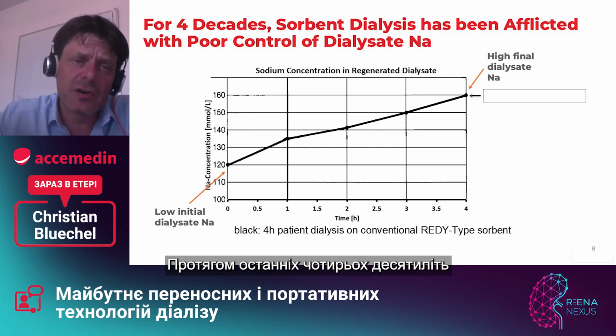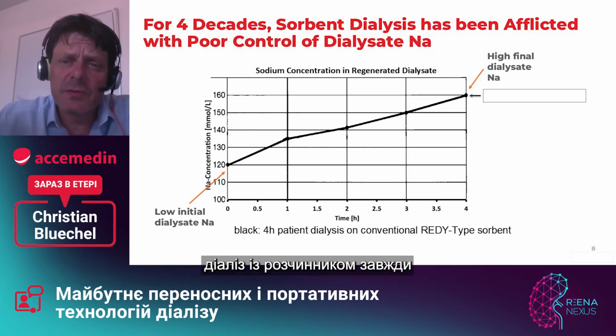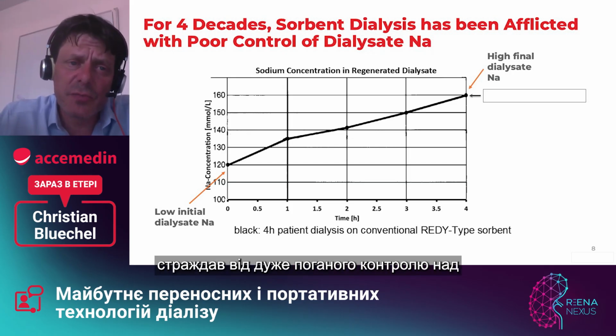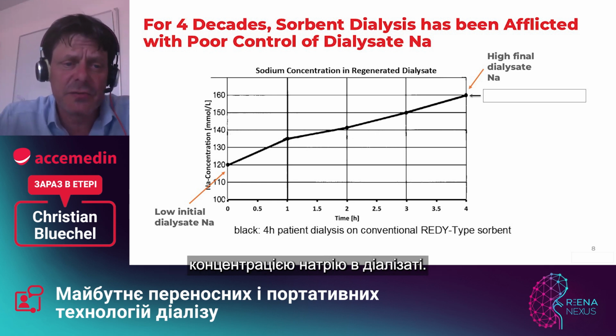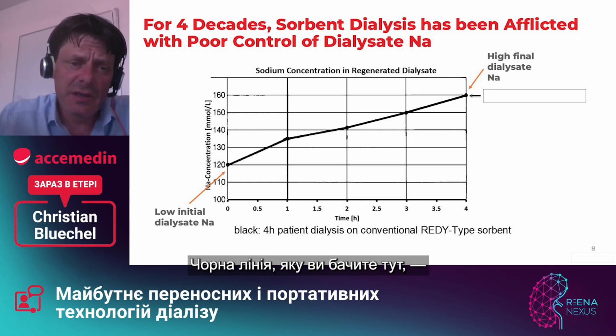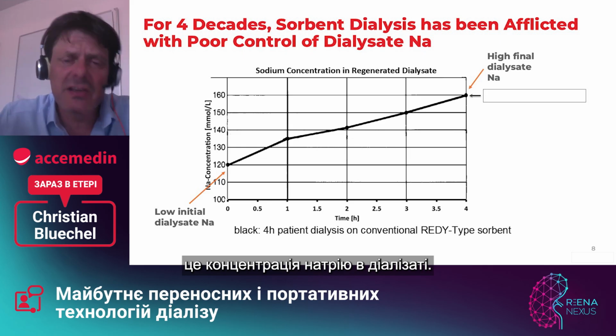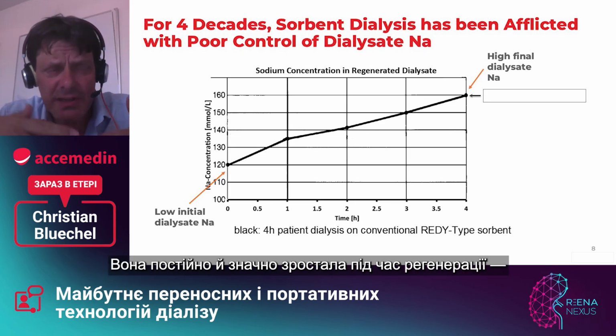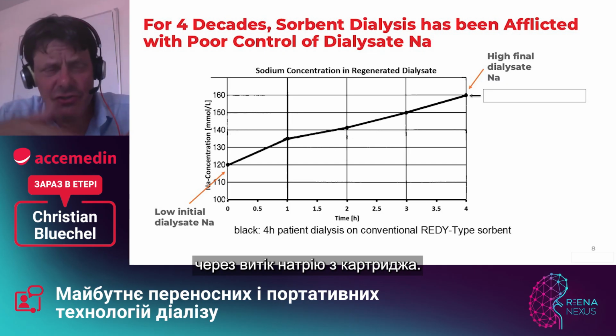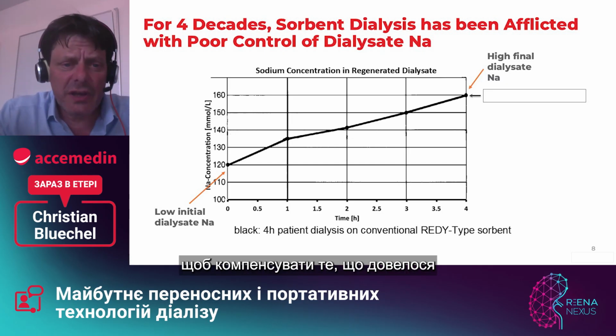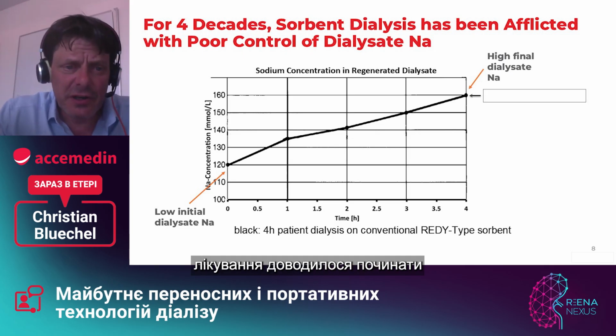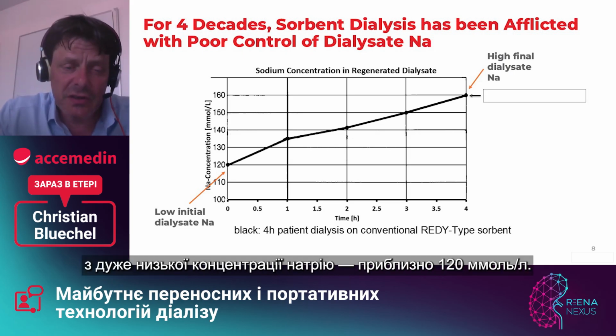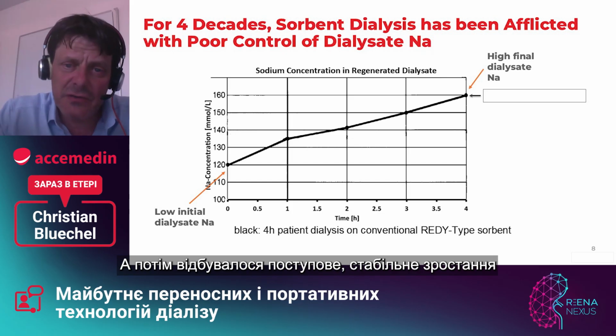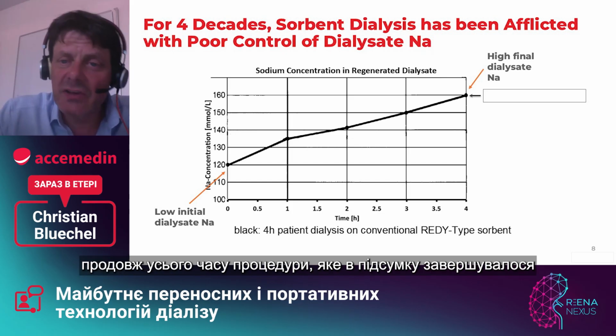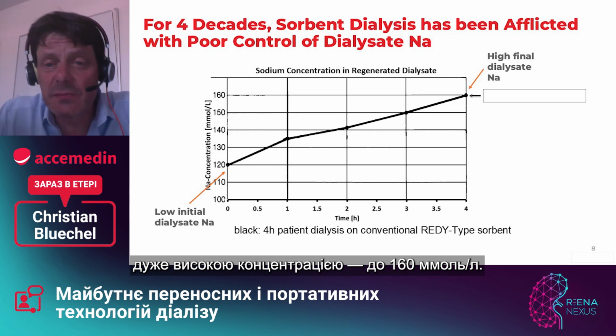So for the last 4 decades, sorbent dialysis has always been afflicted with a very poor control of the dialysate sodium concentration. The black line you see here is the sodium concentration in dialysate. There was a constant and significant release of sodium from the cartridge during this regeneration process, and in order to compensate that, one had to start the treatment with a very low sodium concentration, 120, and then there was a gradual steady increase over all the time and ended up at a high concentration of 160 millimole per liter.